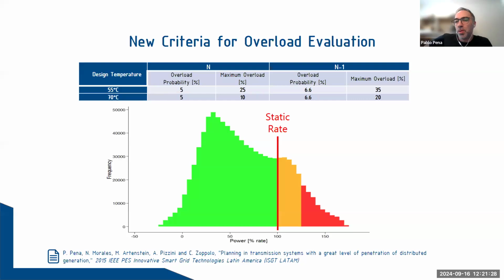By solving the AC power flow of the representative scenarios, we obtain this type of results for each branch, for each line, underground cable, transformers. This methodology not only helps us to predict the maximum expected flow across each branch of the network, but also assess the probability of potential overloads. Being able to estimate this probability, we have established new criteria for evaluating overloads, which could enable us to enhance line capacity by as much as 25%, while the likelihood of overload remains minimal, and we have a safety margin.